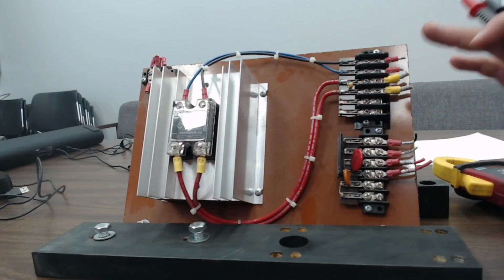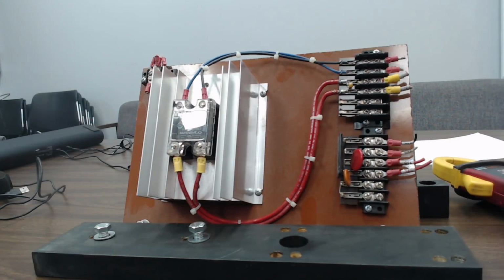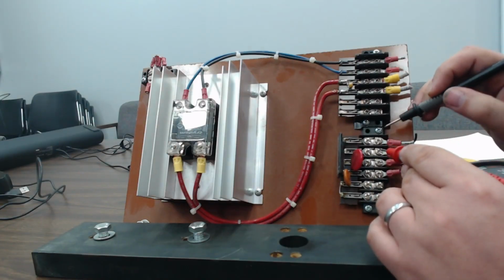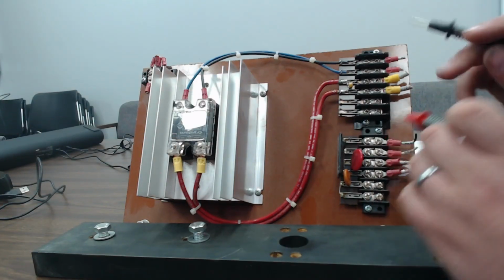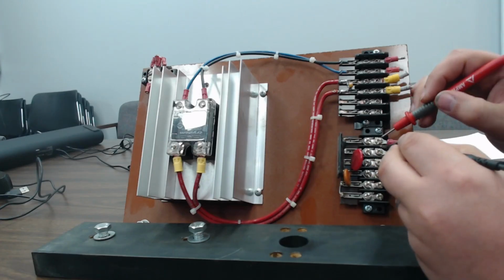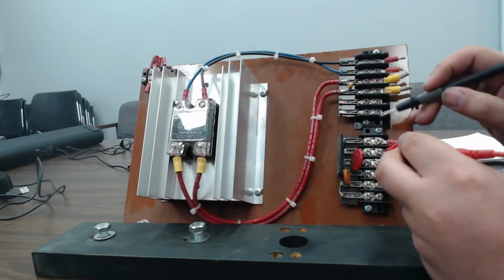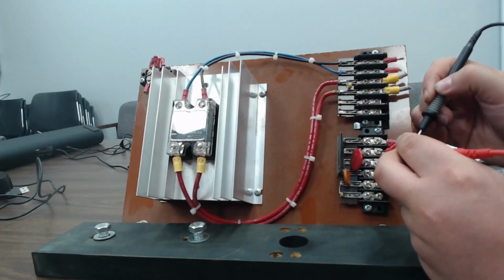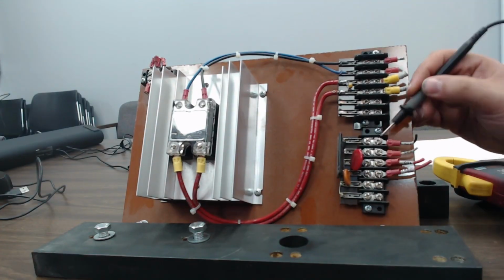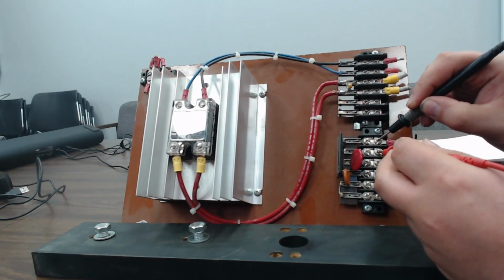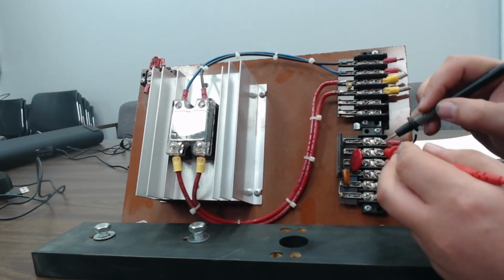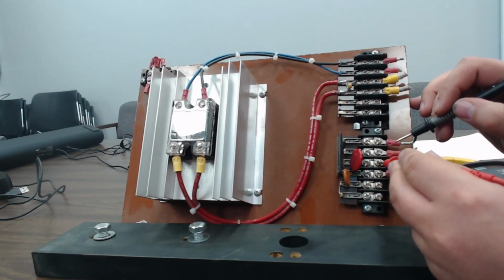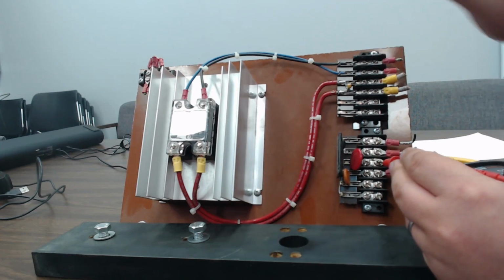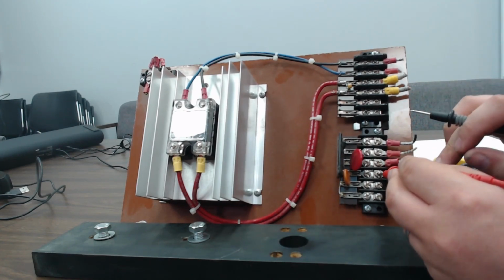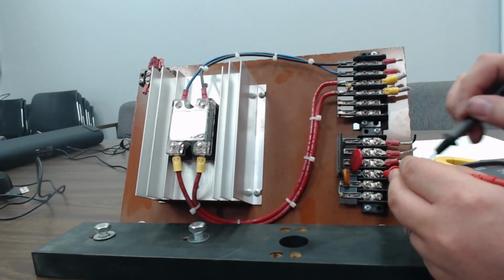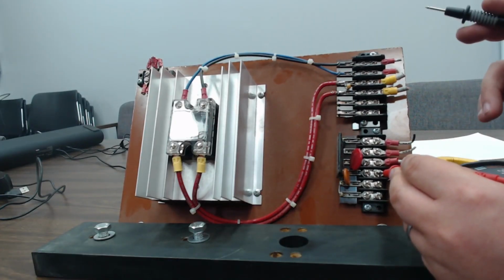So I'm going to go over that very briefly. When we talked about the 0 to 3 volts, raising it up, it's the same thing. Black is still negative, white is positive. Oops, there you go. So right here, these two wires, I know it's cut off, but that is what you are checking, right here and here. You're checking for the 0 to 3 volts. That should be turning this unit on to where 120 is always on live if you're checking to the neutral. And then the wire down here is going to be the 120 going out once you hit the on button on the meter.